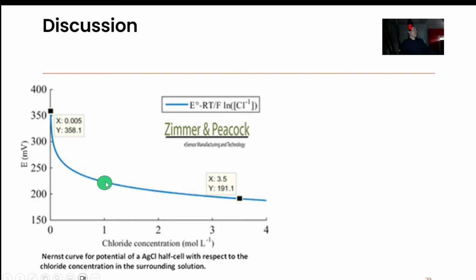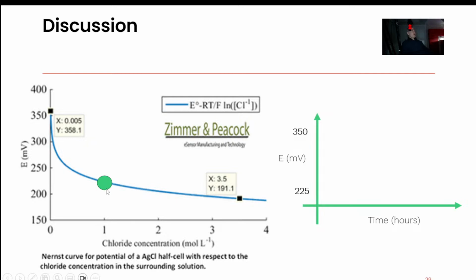I'm realizing now that over the last couple of years, I've really changed my thinking on this a little bit. Because what can happen is you load it up, and if you put it into a solution that's very low in chloride, chloride is a very mobile anion. It's quite small, singly charged. You can't hold it in place. It's going to diffuse away, at which point the chloride concentration on that electrode can diminish, and its reference potential changes. I've shown it here: if you go from 1 molar to 150 millimolar, the reference potential can change quite a bit, by something like 125 millivolts, which would really mess up a potassium sensor and even a glucose sensor because the potential is not fixed.